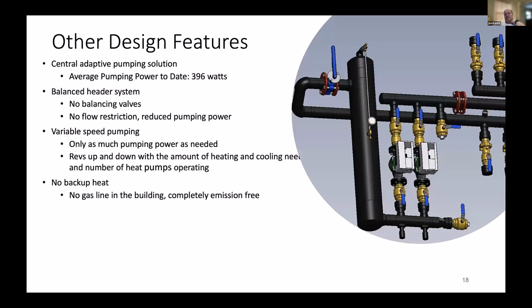Then the other design feature here is that we have an adaptive pumping solution. You can see here a flow center purging all the air out continuously and providing the flow to the two heat pumps, to the two circulation pumps here. They're pressure regulated. They sense the back pressure on how many heat pumps are actually online, and they adapt accordingly. So the average annual pumping power is only 396 watts that way. And that is, I feel, a very unusually low number.